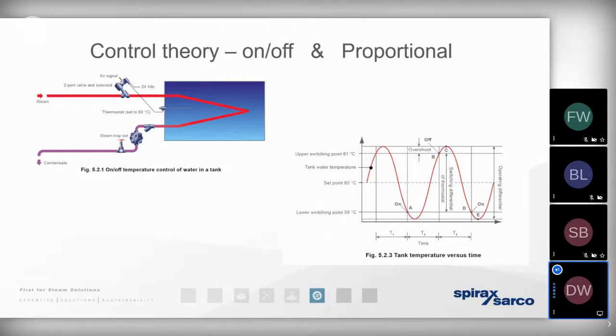But we can improve on that by moving towards proportional control. And that's what's commonly featured within a self-acting valve. And that's where the valve opens and closes in proportion to the required temperature change of the process. So for example, if the process is only calling for a little bit of energy or a small temperature rise, then the valve's going to open incrementally. So if we're using a tank of water that's using a steam coil to heat it up as an example, if it's got a set point of 60 degrees, that means the valve could start to open at 59 and then start to close at 61. So we'd refer to that as having a 2-degree proportional band.